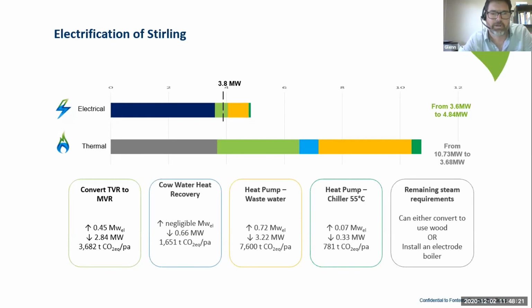It looks like it's gone up about 800 kilowatts or thereabouts, and you can see a corresponding reduction in the thermal bar - the same light green color in the thermal bar is the reduction. So for a relatively modest increase in electricity, only half a megawatt, 450 kilowatts, there's a pretty significant reduction in the amount of steam use on site. So that's a pretty big one.